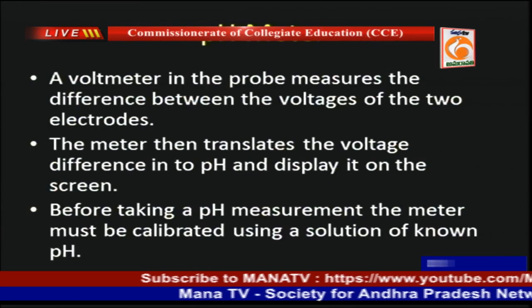One needs to understand that an ion exchange phenomenon is taking place. The glass electrode, which is also built with certain metals and silver chloride, comes into contact with H plus ion concentration. If the H plus ion concentration is more in the analyte solution, it will be called more acidic. When you dip your electrode in that, exchange of ions will take place in such a way that H plus will go inside and certain ions will come out. Here, my dear students, you need to understand that ion exchange is happening. The millivolts across the electrodes are determined and converted into pH, which is the fundamental basis for this. All of us know we need to clean the glass electrode properly, keep it separately, standardization to be done, everything.